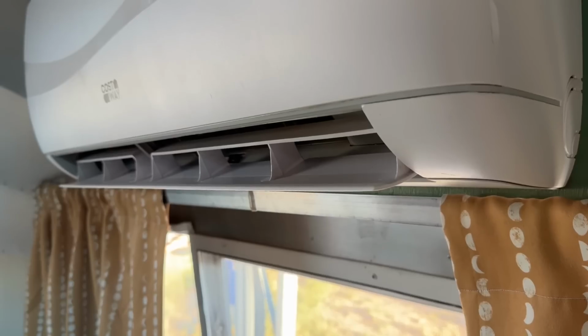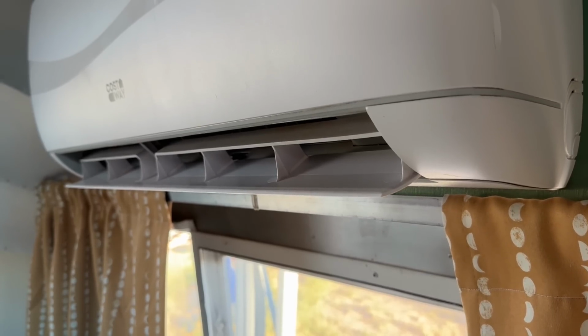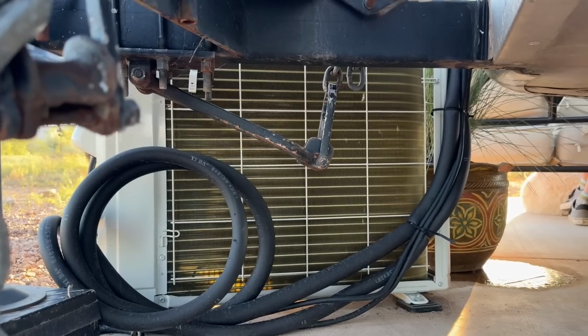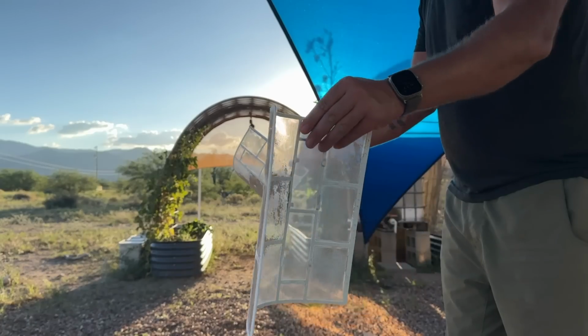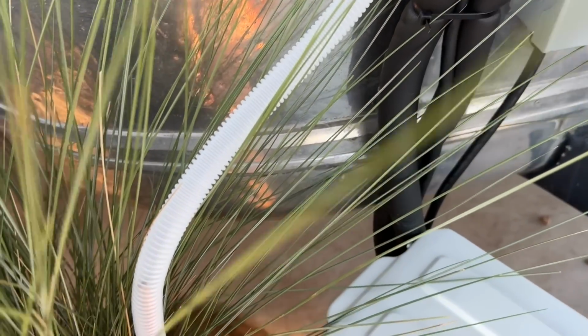That being said, we do know several people who have installed these mini splits on a trailer that moves without any issues. Yeah, most of the problems that come with a mini split are not the hardware itself, it's with the install. And finally, like any AC, these do need maintenance. The condensation tray tube can get clogged and back up into the inside, so it's important to clean your coils regularly, clean the dust filters, and vacuum the drain often. We've definitely sucked a few bugs out of our condensation tube.